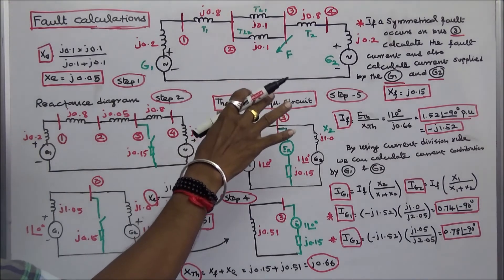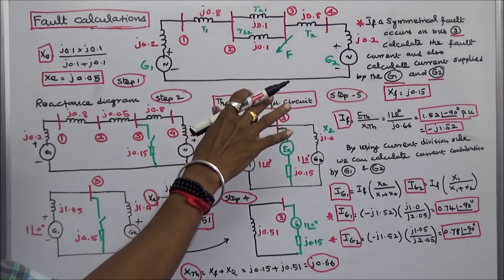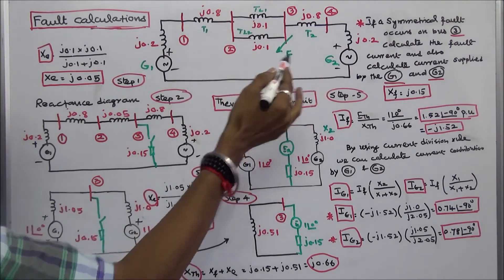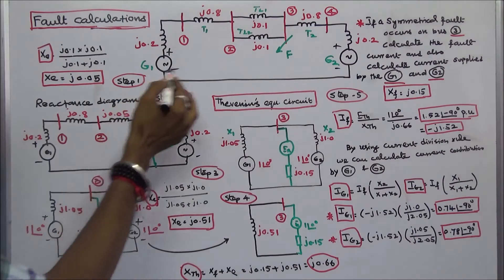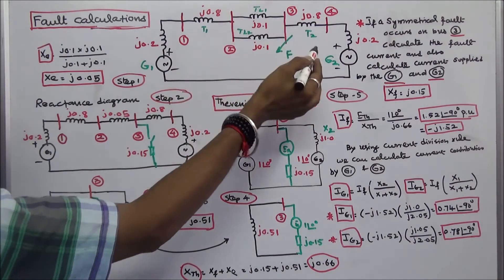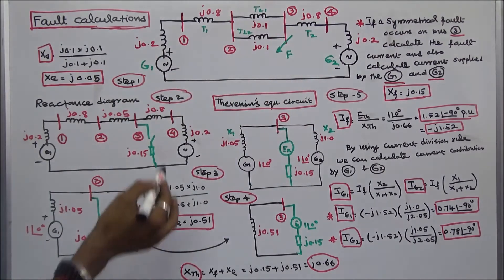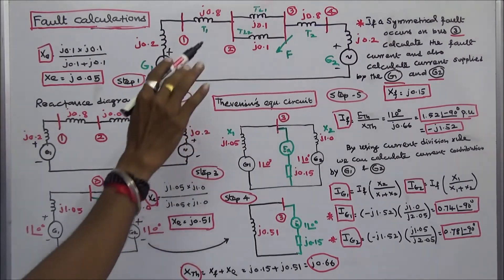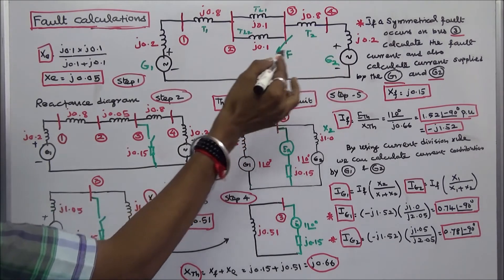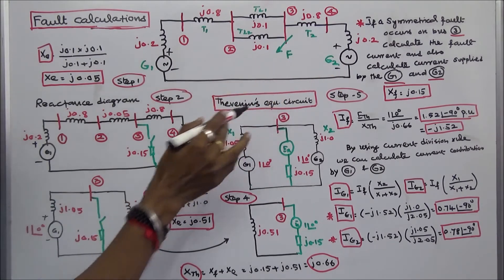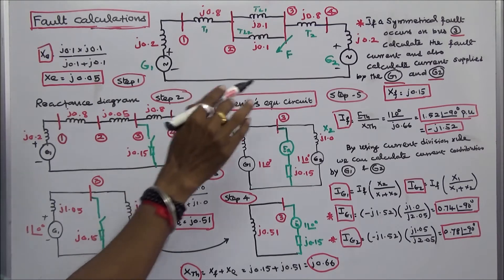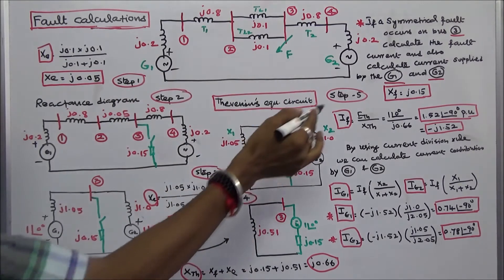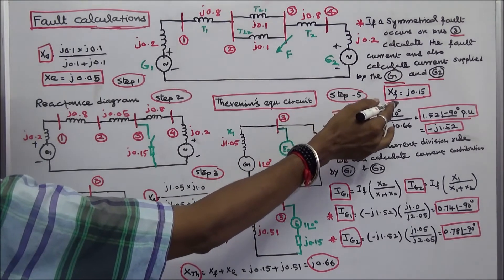In this class we work out one problem on Symmetrical Fault Calculation using Thevenin's Theorem. This is the given network, which consists of two generators, two transformers, and two transmission lines. The reactance values are given, all in per unit. The question is: if a symmetrical fault occurs on bus 3, calculate the fault current and also calculate the current supplied by generators G1 and G2. The fault reactance XF is equal to J0.15.